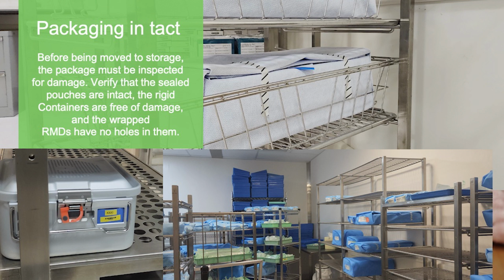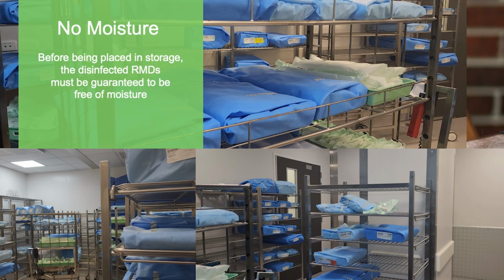Packaging intact. Before being moved to storage, the package must be inspected for damage. Verify that sealed pouches are intact, the rigid containers are free of damage, and the wrapped RMDs have no holes in them. No moisture. Before being placed in storage, the disinfected RMDs must be guaranteed to be free of moisture. This check is completed after the cooling time has passed.